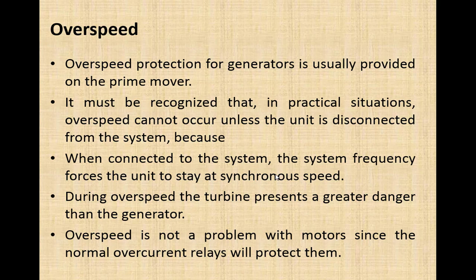If we are operating a motor in overspeed condition at lesser torque requirement, keeping the power output of the motor constant, that is not a problematic situation at all because motors are designed to operate at some higher speed at lesser torque output requirement.